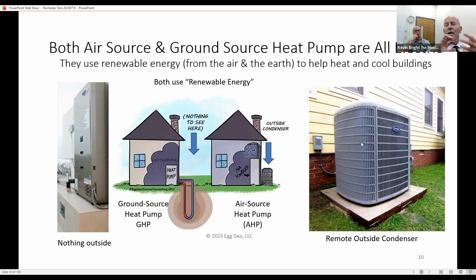Now, the outside condenser is supposed to extract heat from the cold outdoor air in wintertime, and that's fine until it gets down below 20, 10, 0 degrees. What happens with the heat pump when it's trying to extract heat from colder temperatures? It uses more energy, so much more as it gets colder that it quickly moves away from 3, 4, or 5 COP.